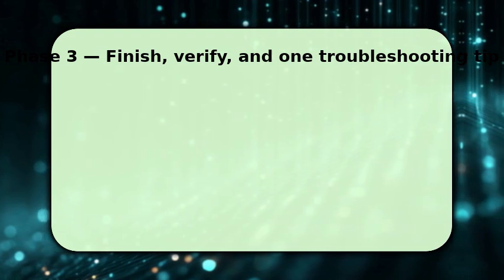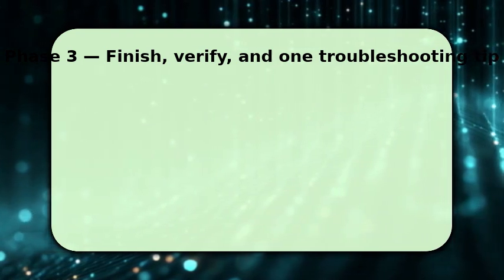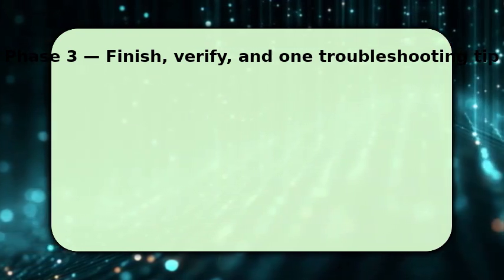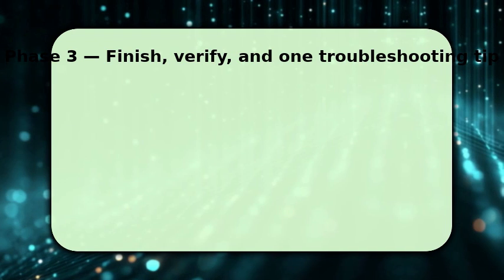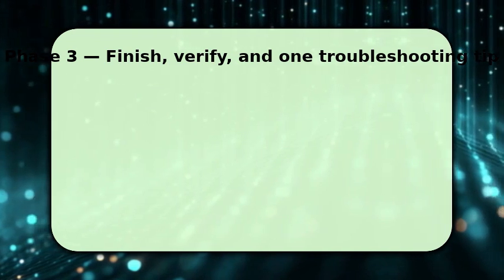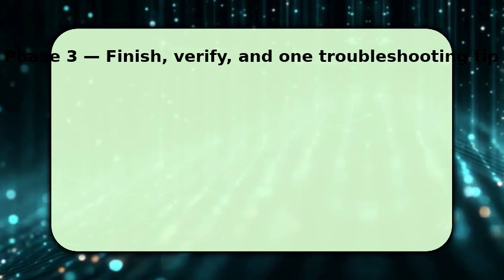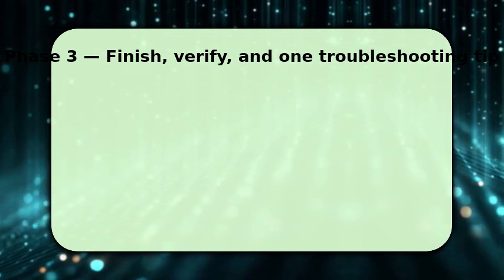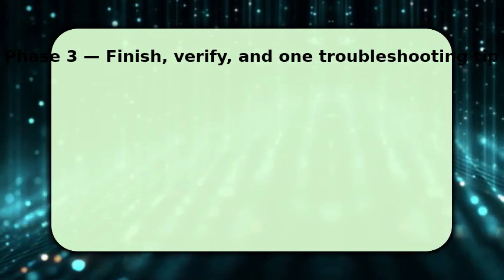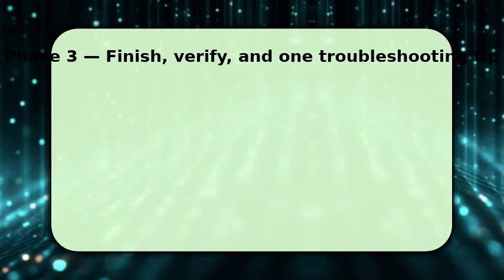If readings are inconsistent, make sure the probe is clean and not fouled, check the calibration solution age and concentration, and verify temperature compensation is enabled. One key troubleshooting tip. If values jump erratically, clean the probe with mild detergent, then recalibrate.